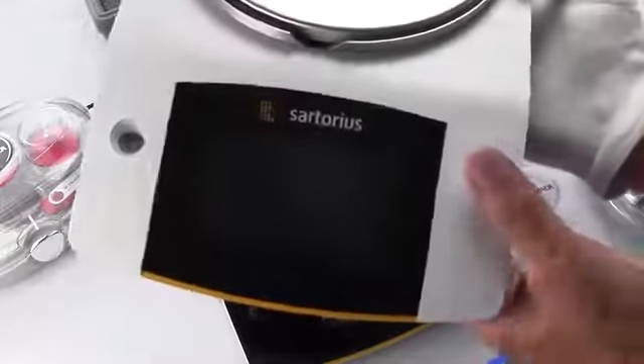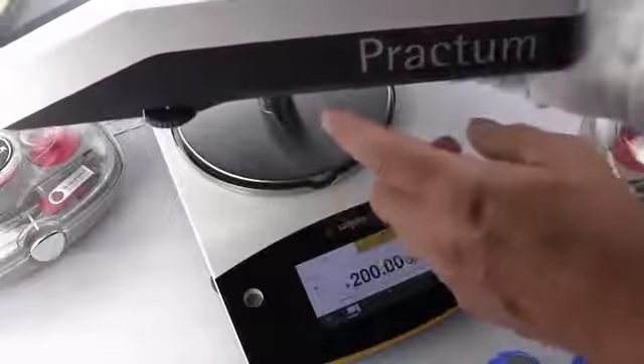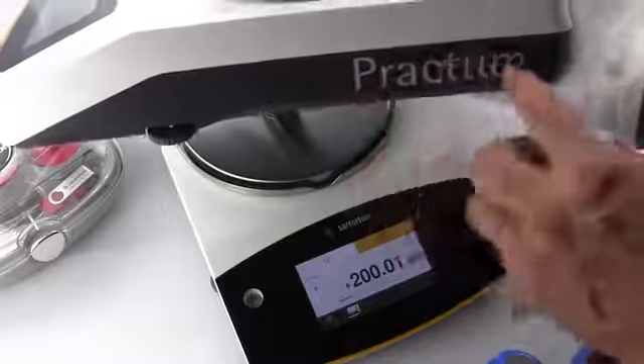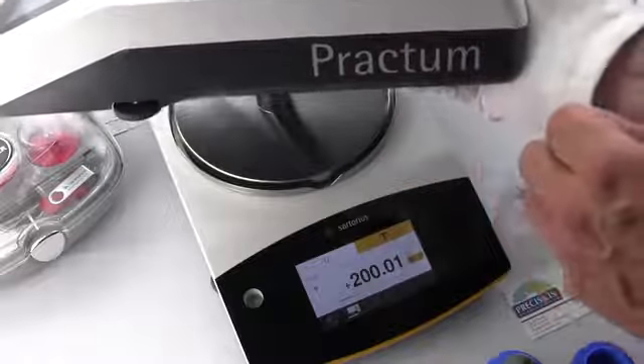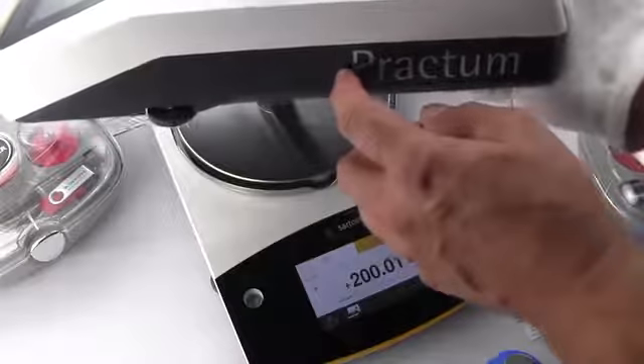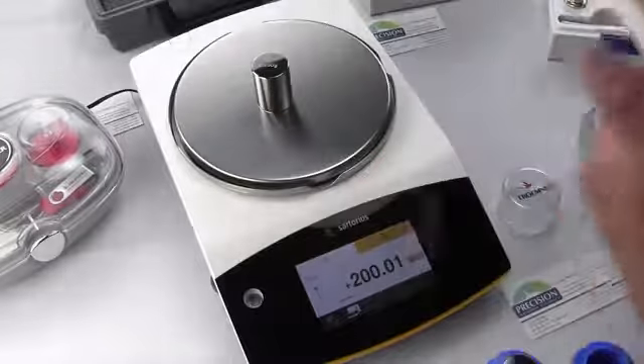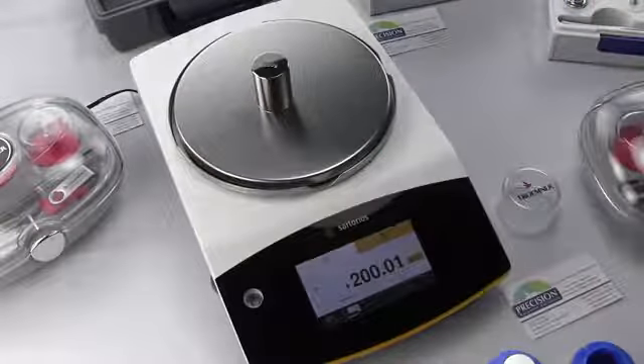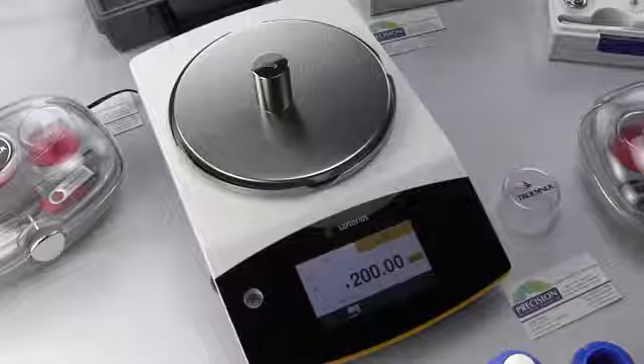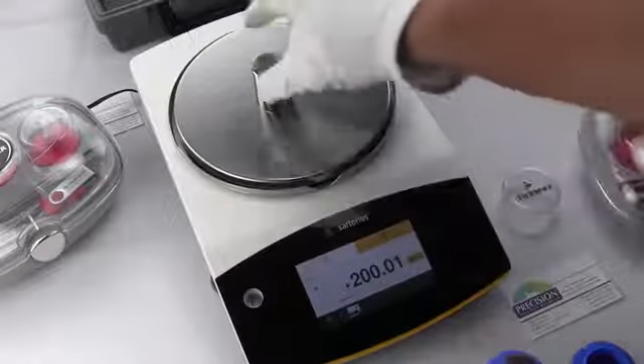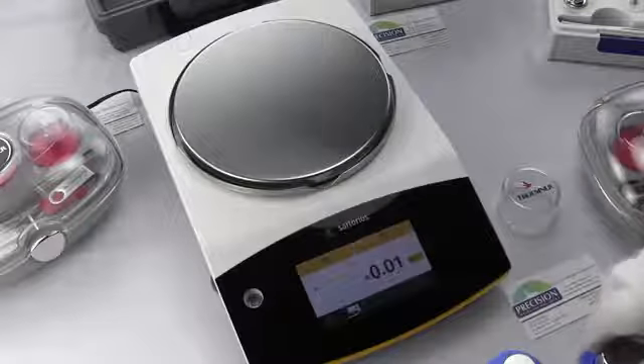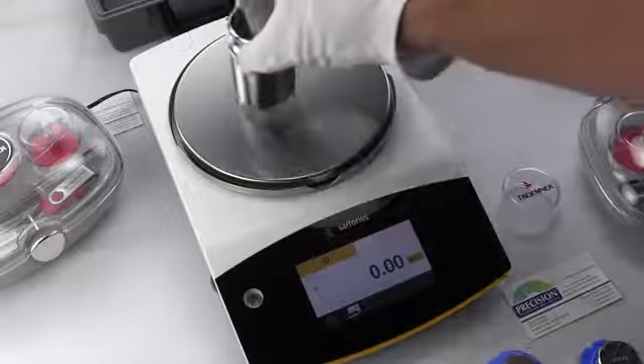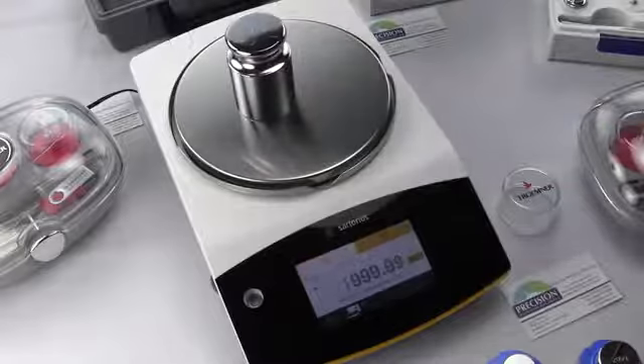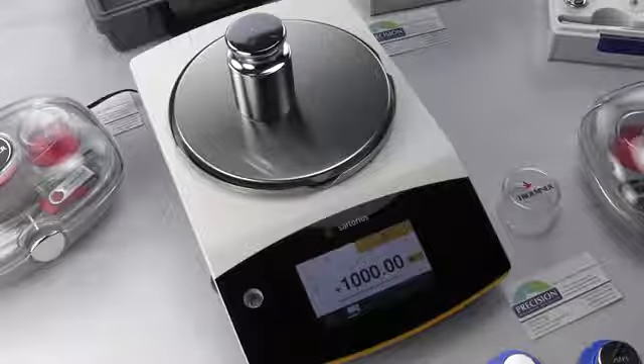Now the Practum series has a very similar body style, but on the side you'll see Practum, versus if you had a Quintix, it's going to say Quintix or Secura. The Practum is only external calibration. During calibration, each model requires a specific calibration weight, and this is all specified in the manual.